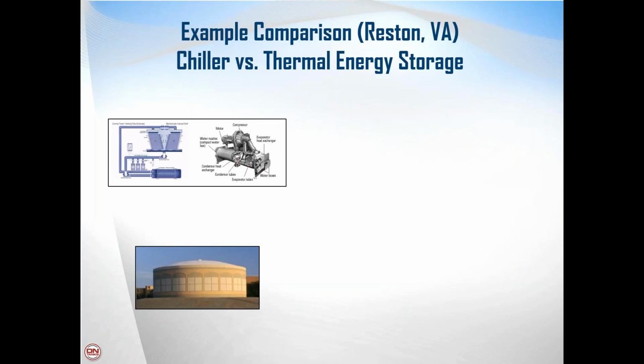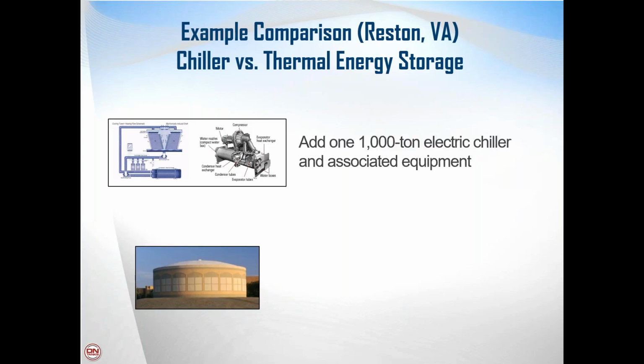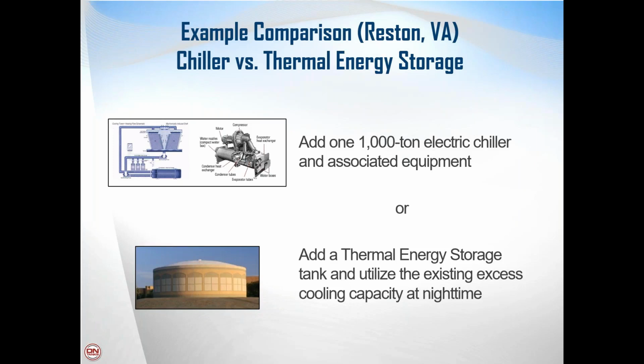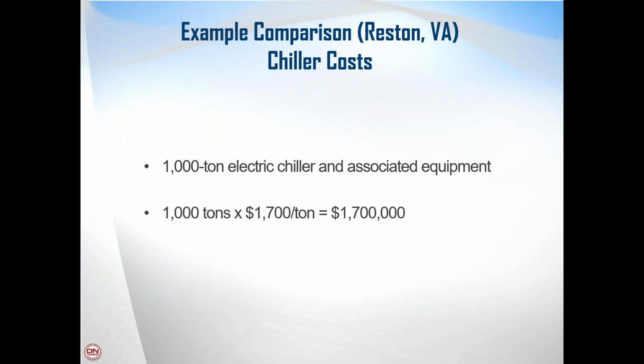I'm now going to go through an example. This is a real-world example on a project that we're working on with an owner in Reston, Virginia. But this type of application is one that is common across the country. The owner is looking at replacing a chiller and a cooling tower at their campus. And it's a 1,000-ton electric chiller with associated equipment. And they're also considering, instead of that refrigeration equipment, can we just add a thermal energy storage tank to the system? So it's a question about a 1,000-ton chiller versus a thermal storage tank.